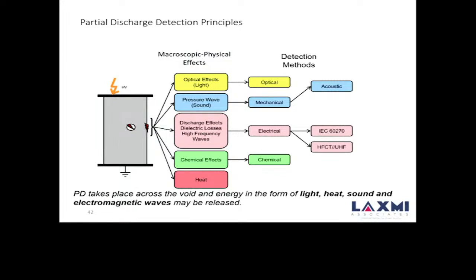Again, in the morning we discussed this. If you have a partial discharge, that means electrons are moving inside, there is a conduction. So electron movement is very high in a localized area. When this is the scenario, what is happening? You have different impacts of such movement and bombardment of electrons because of the charge, and you see the polarization. So the first thing is light, which you see in the form of corona. You see a pressure wave. A pressure wave means vibration in the insulation structure, which you capture by acoustic PD.